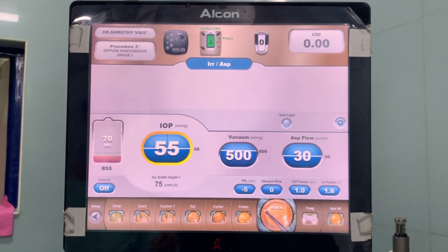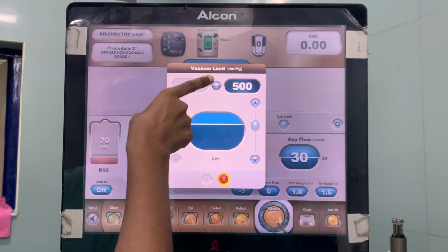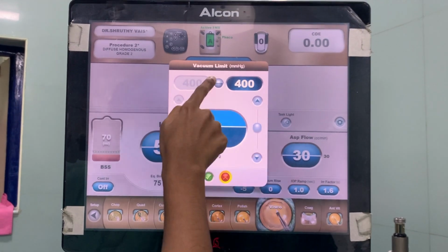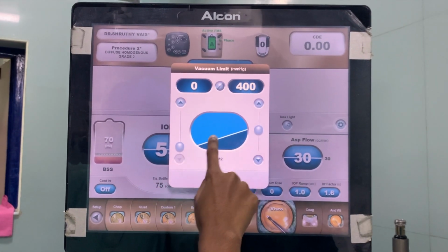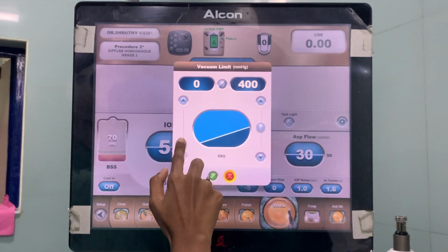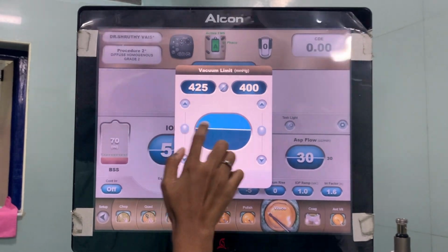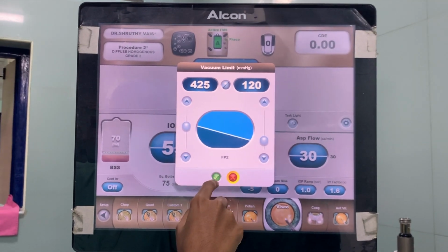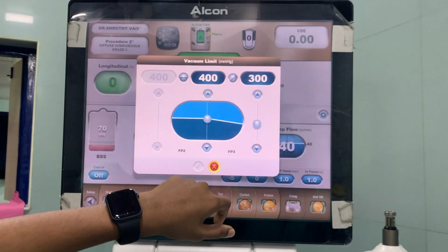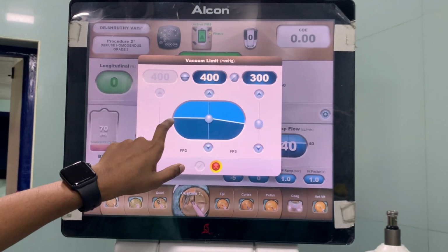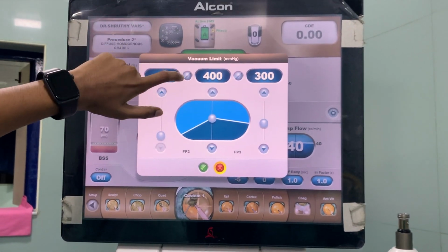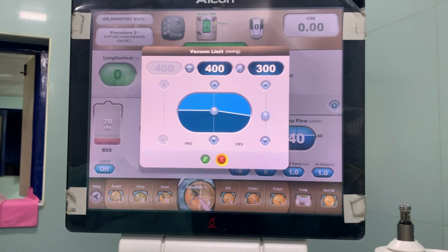Active fluidics technology is designed to allow the use of much higher fluidic parameters than on gravity fluidics. By pressing the knob, the vacuum can be shifted to linear mode or to reverse linear mode. The advantage here is that during nucleus management, the vacuum settings can be altered between foot position 2 and 3, which provides more control and reduces the post-occlusion surge.